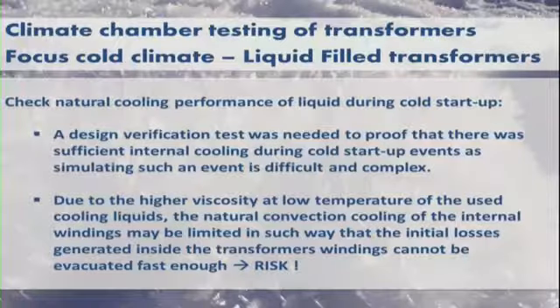The second thing we want to test: you would imagine that with this very cold temperature, cooling is not a problem, but it can be. Why? The oil, the cooling medium, becomes very stiff, and it could lose its performance for natural cooling convection. We need to bring the heat from the windings to the fins of the transformer, and because the oil is very stiff at that moment, we have to validate whether this is really happening. That's to mitigate the risk and to be sure that the design is right. This is very complex to simulate, which is why you test this.